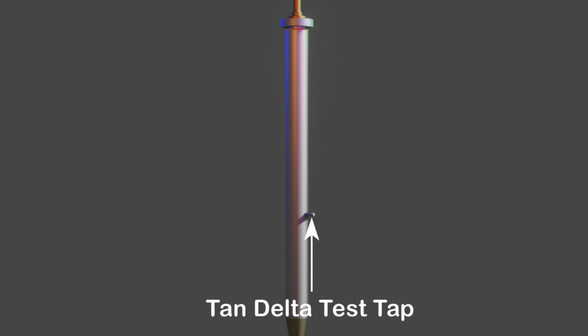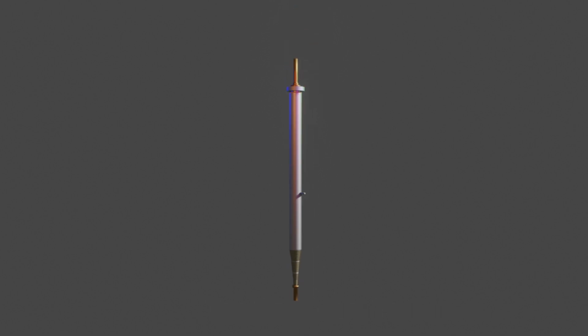This test tap lets technicians measure the capacitance and tan delta of the bushing. In simple terms, it's how we check the health of the insulation. If the tan delta value goes up during operation, it tells us that moisture or damage has crept into the insulation, a sign of deterioration.